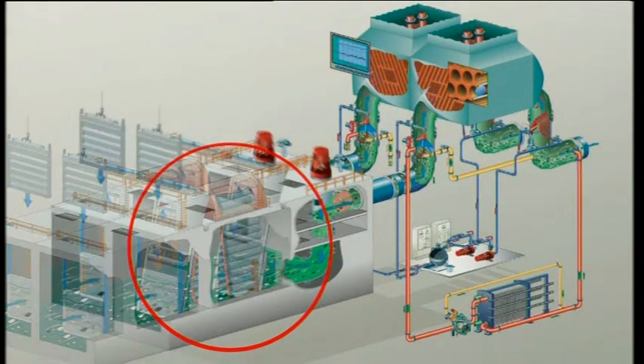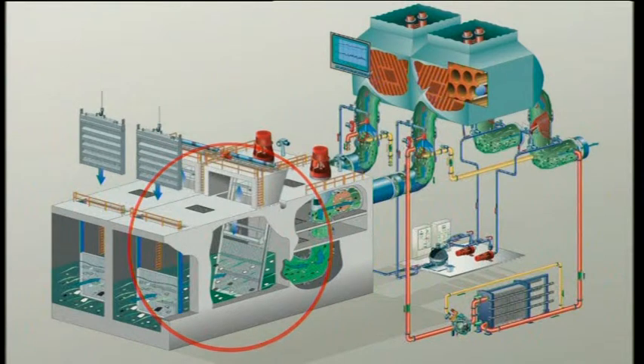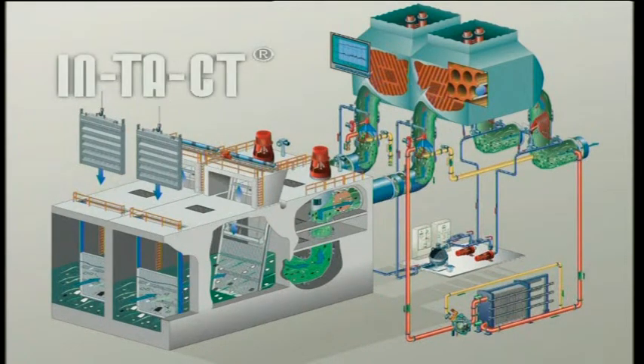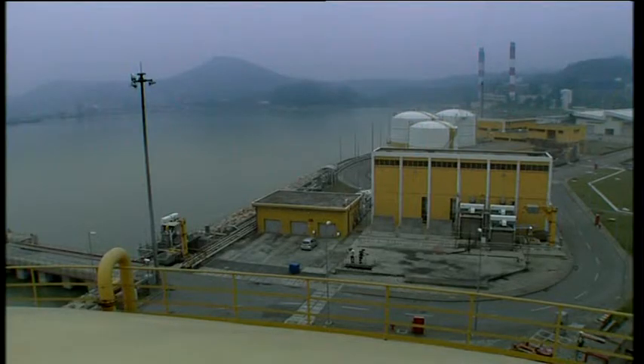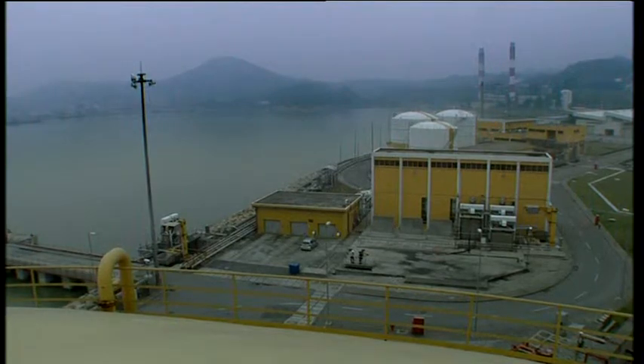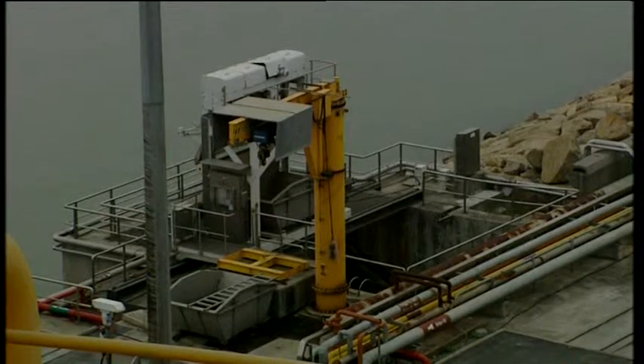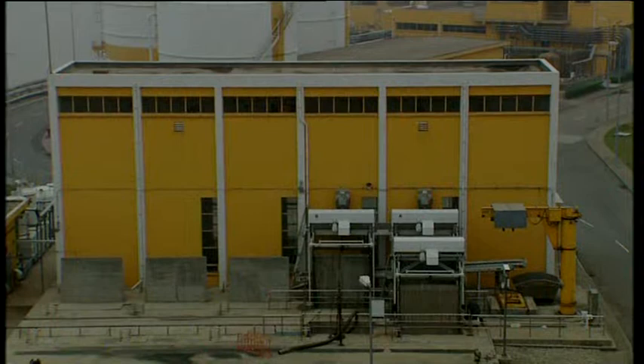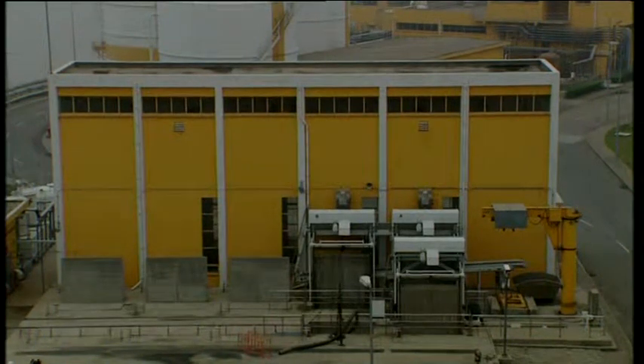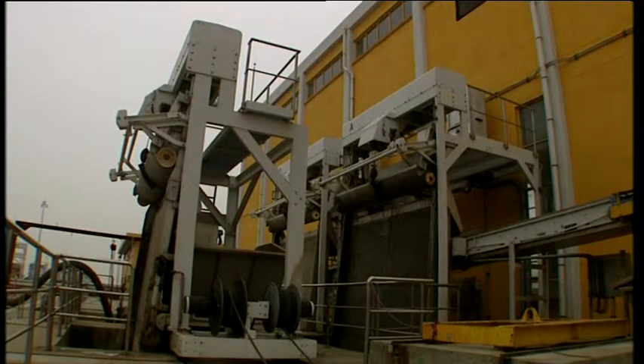This revolutionary concept of a lean pre-screening system focusing purely on pump protection, combined with high-performance filtration technology and tube cleaning, was called IN-TA-CT, the integrated Taprogge concept. As an integral part of IN-TA-CT, the pre-screening system, henceforth consisting only of coarse screens and fine screens, made its way into Taprogge's responsibility and scope of supply.